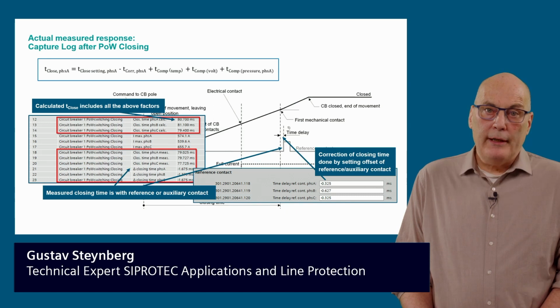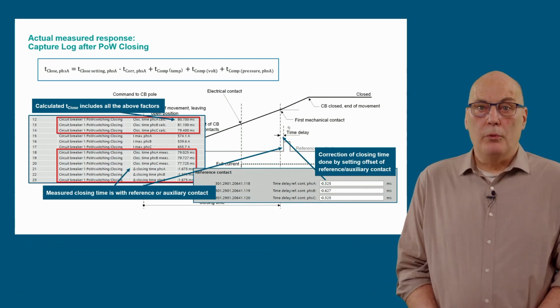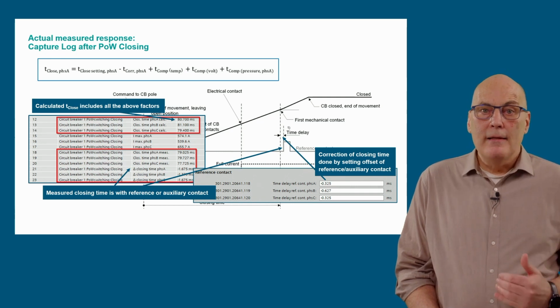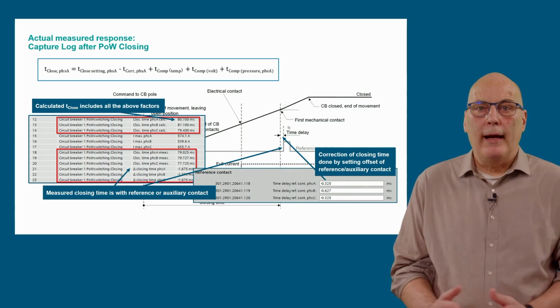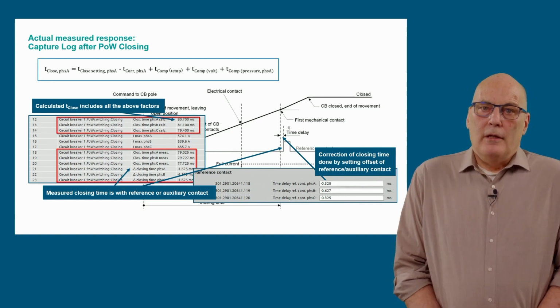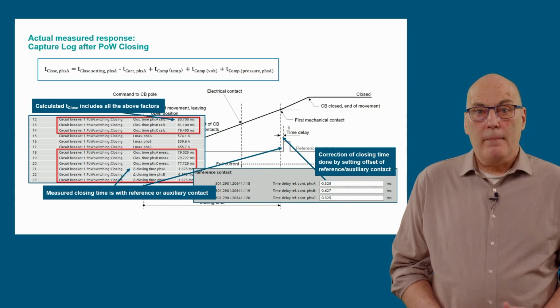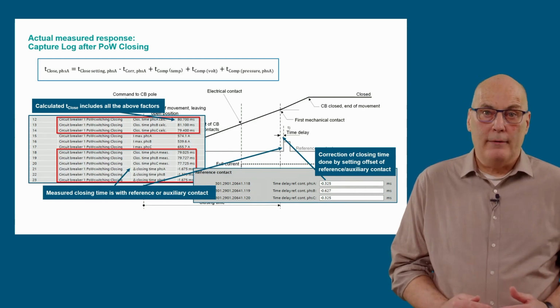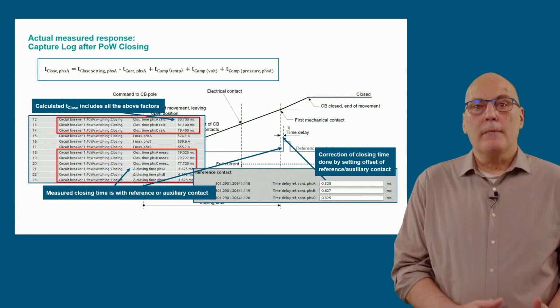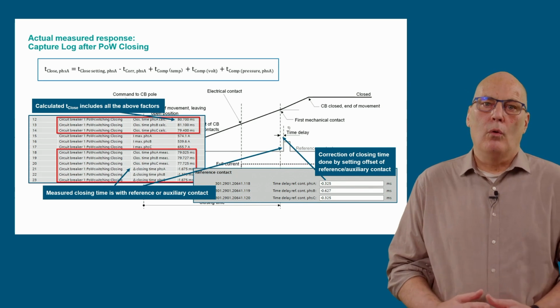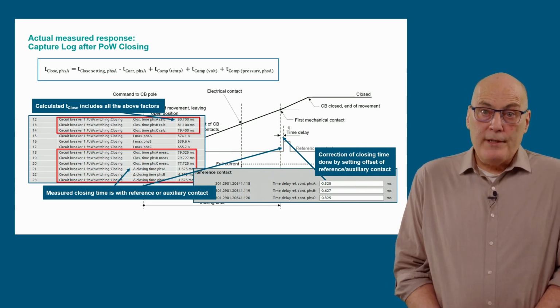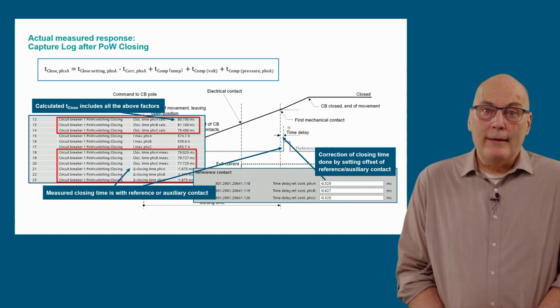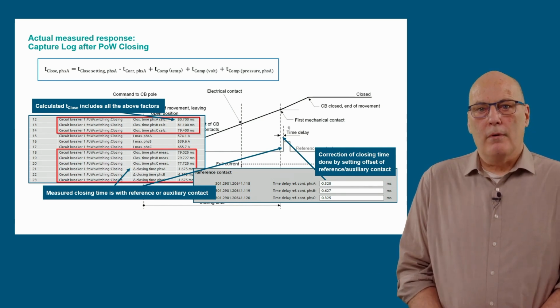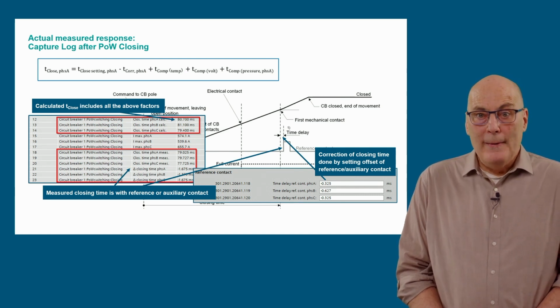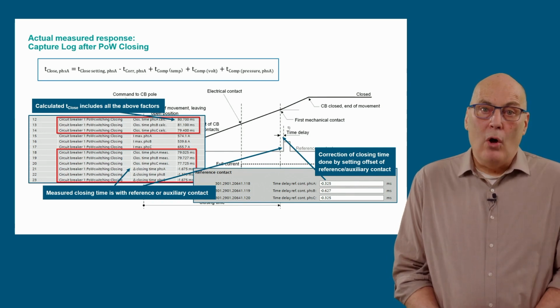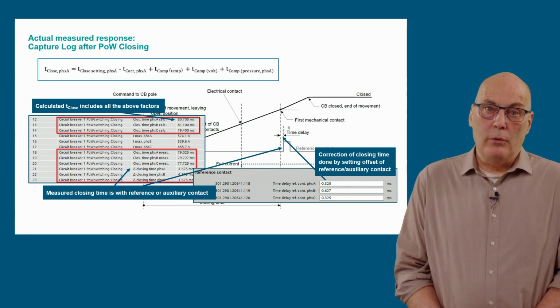A delta value is also indicated for the closing time, e.g. minus 1.675 milliseconds for phase A. This is simply the difference between measured and calculated closing time. The assumption is that the calculated closing time as per circuit breaker data is correct. The deviation of the measured closing time is due to offset of the reference contact or auxiliary contact. This offset can be compensated by changing the reference contact time delay as shown in the settings at the bottom right-hand side. Note, this reference contact time delay does not affect the calculated closing time. See equation at the top.